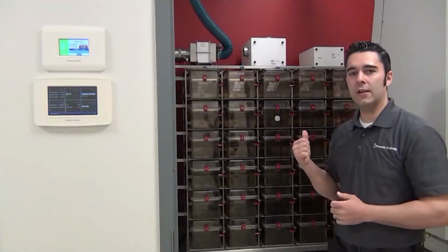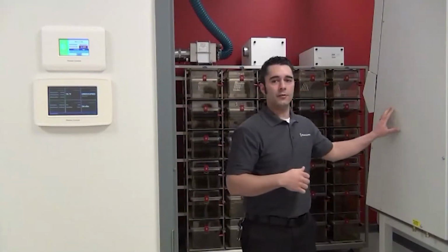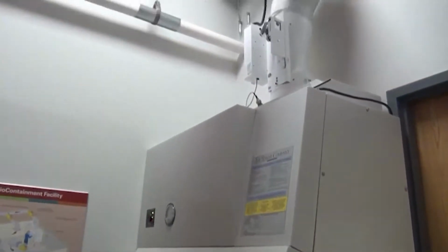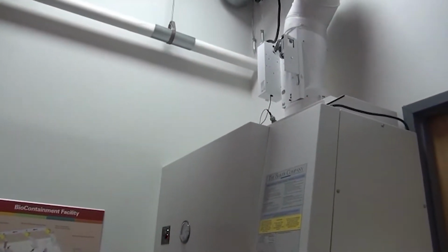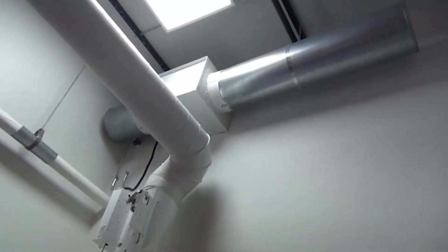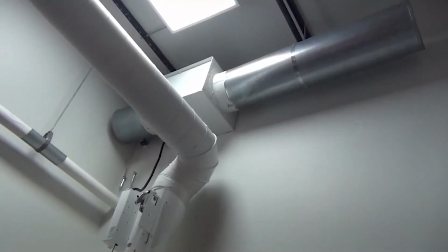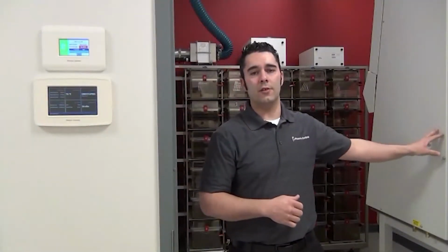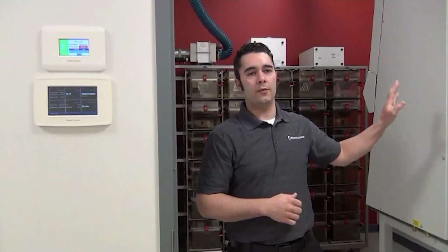In addition to the cage rack we have in the space, I also have a biosafety cabinet over here, and effectively how the biosafety cabinet works in this environment is a recirculating hood with a filter and a blower in it. So the Phoenix Controls valve that we have on this is a shutoff valve, a low leakage shutoff valve, so that when this hood is in its shutoff mode and it's decontaminated, there is virtually no air going through that valve. The Phoenix Controls shutoff valves, when they're used in their low pressure applications, have a gasket on the cone, so when they're in shutoff mode, they leak 0.005 CFM.